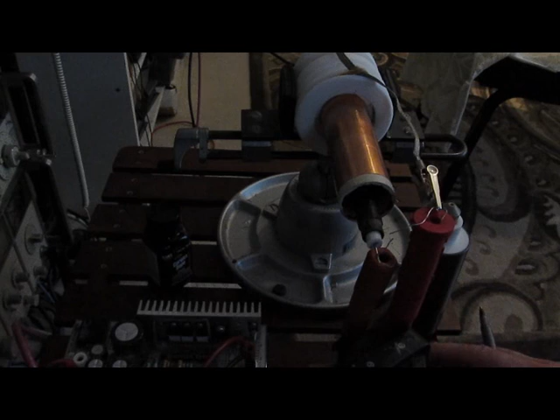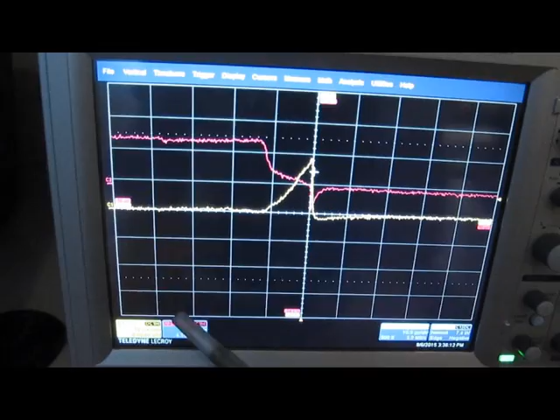Okay, so I'm going to slowly start increasing the gap here. It's a fairly large gap now, about 1/4 of an inch or so, maybe 3/8. This is currently 10,000 volts per division here. So you can see we're at about 20,000 volts and everything looks fairly normal. Again, the output looks fairly smooth. This is pretty much what we'd expect to see right now. So yeah, 20,000 volts does not seem to be a problem.